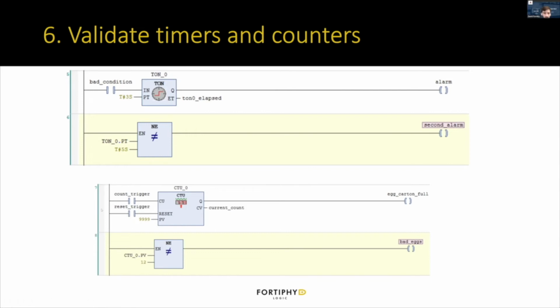And in a similar way, we have some kind of counter block counting something on the production line, and we want to verify that the preset value it's supposed to be counting up to has not been modified. We can have an extra check for the preset value equaling 12. And in this case, again, it looks like someone's modified it. It's not the right preset value. And so we could raise an alarm on that difference.